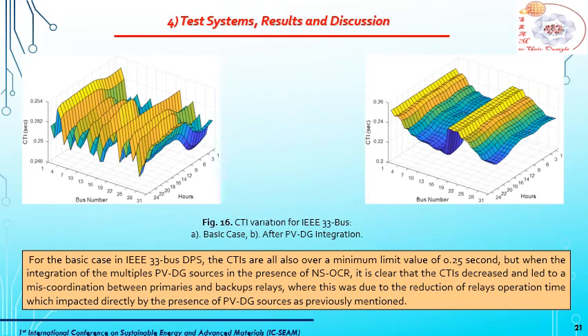Figure 16 represents the coordination time interval variation for the second test system, where the same remark is made after the integration of PVDG into DPS. The CTIs decreased under the minimum limit value of 0.25 seconds and led to miscoordination between primaries and backup relays.